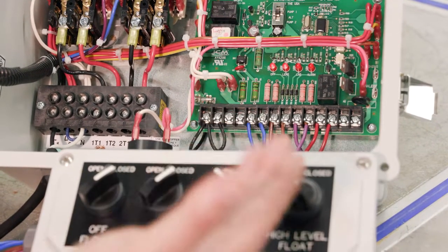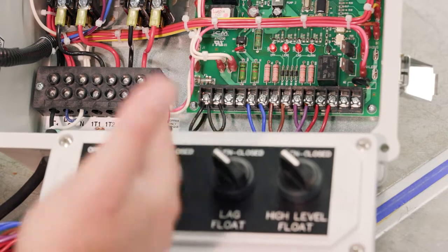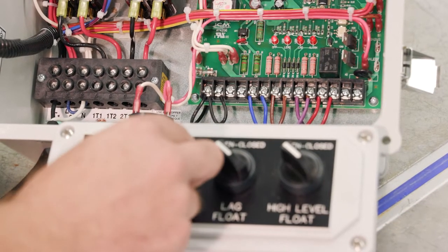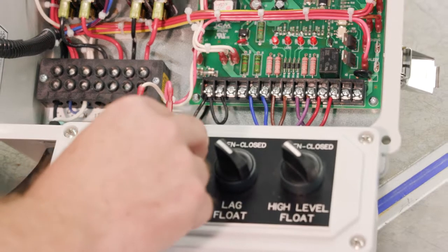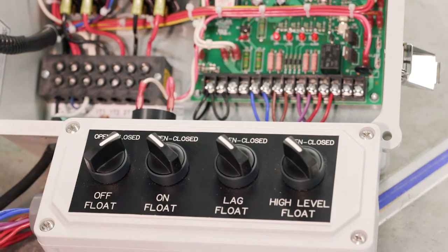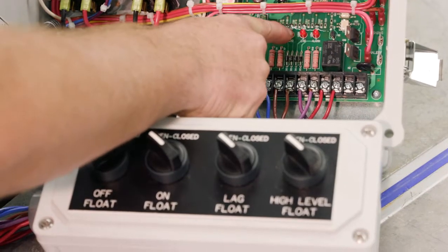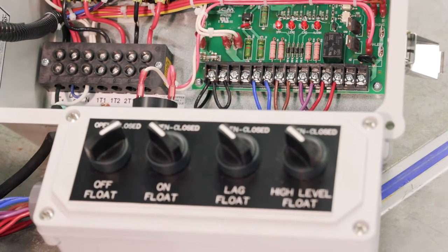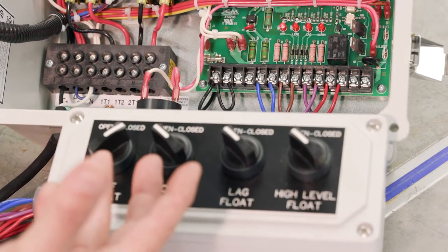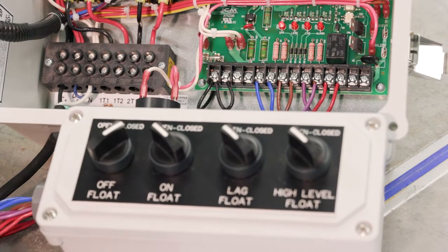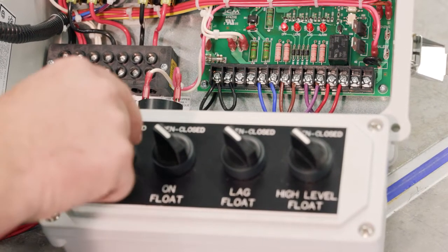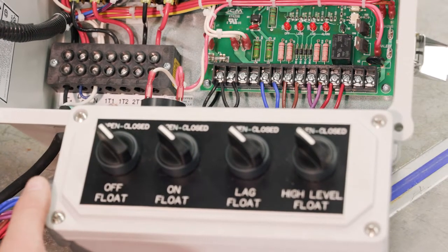Okay, so let's say in this case, pump two does its job. The tank is emptying. This float is going to close first. And notice what happens. The LED light goes off, but the pump is still running. So it continues to pump it down, and then it gets to the first float, which is the off float, turns the light off, and after a delay, it turns the pump off. So so far, so good.